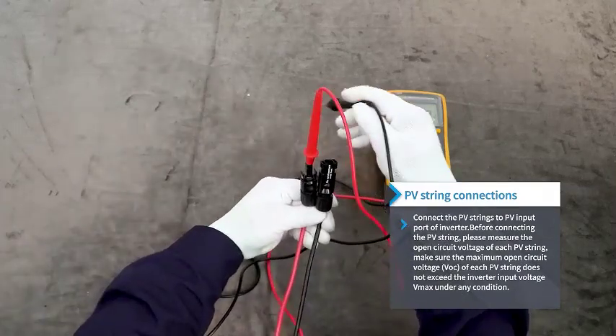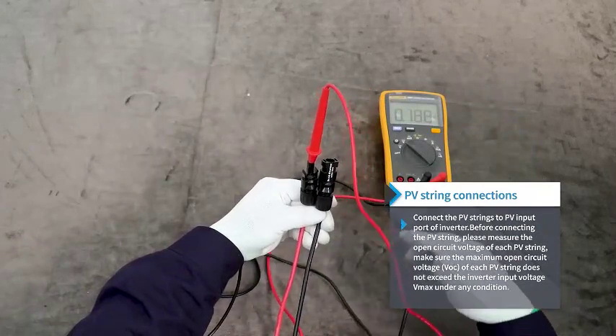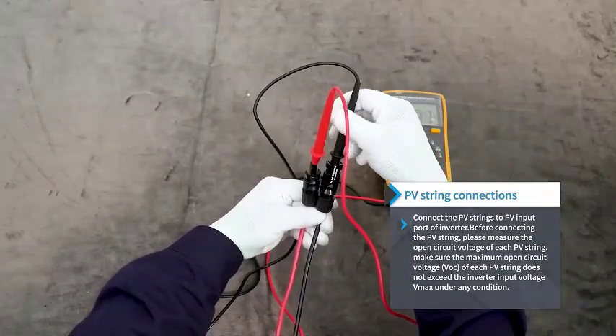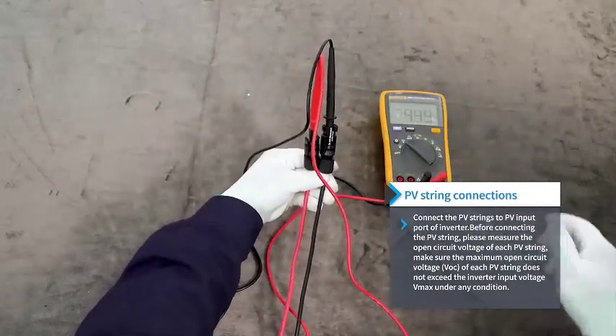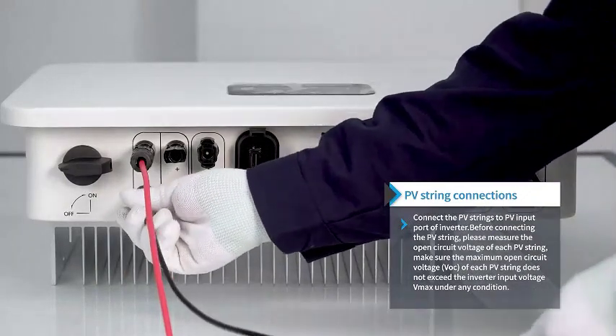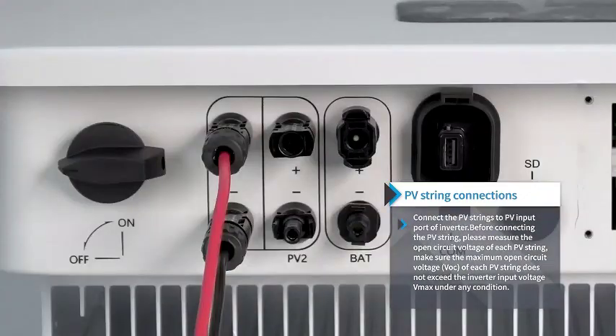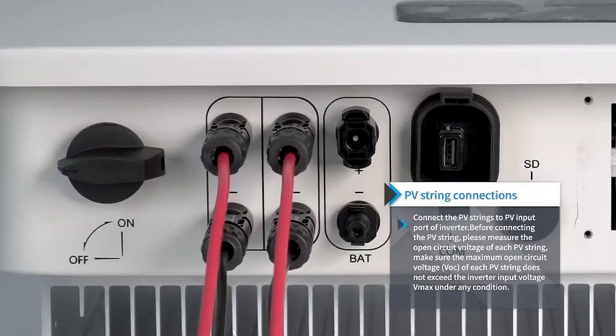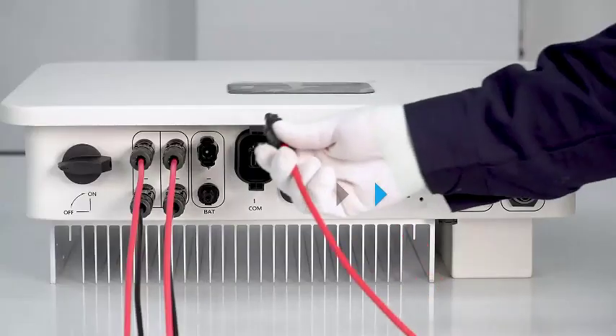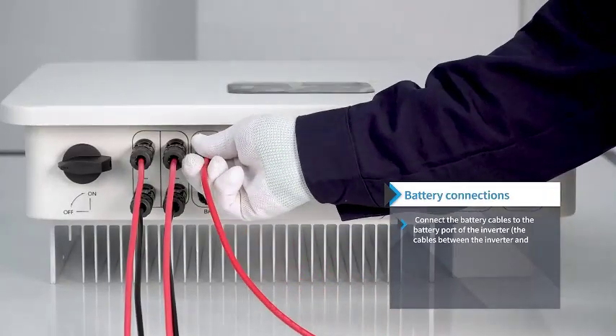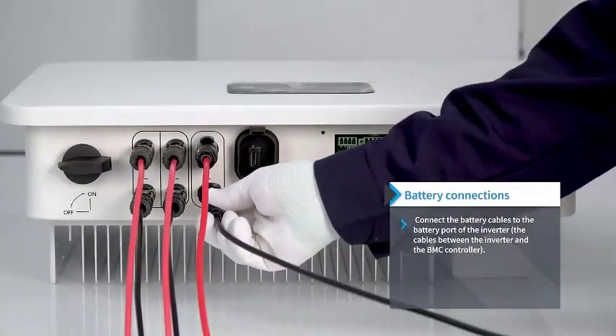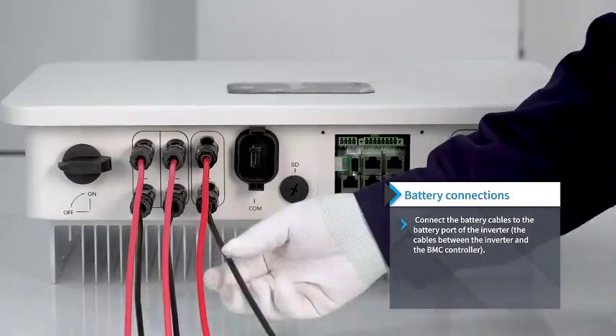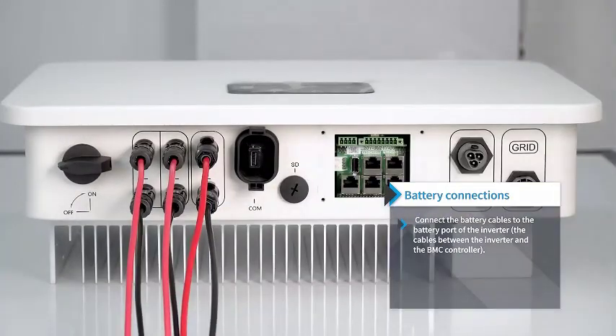Before connecting the PV string, please measure the open circuit voltage of each PV string. Make sure the maximum open circuit voltage, VOC, of each PV string does not exceed the inverter input voltage Vmax under any condition. Battery connections. Connect the battery cables to the battery port of the inverter. The cables between the inverter and the BMC controller.